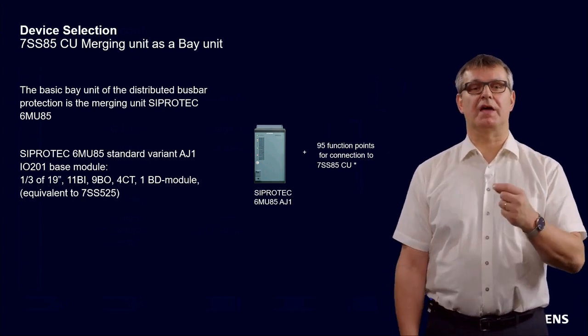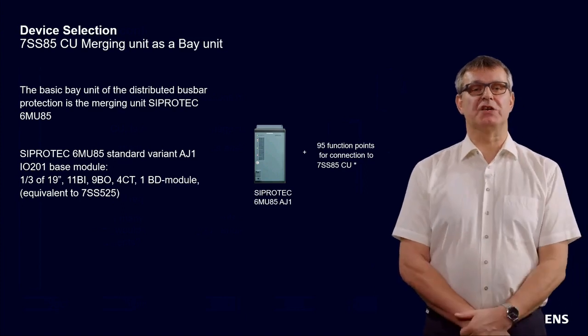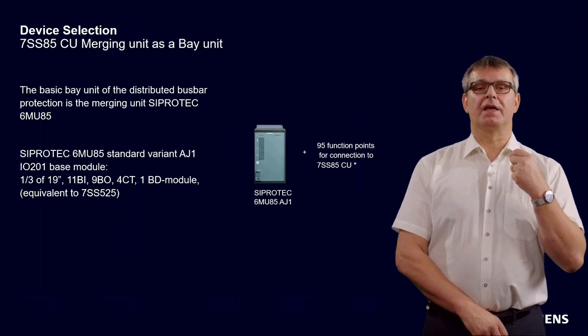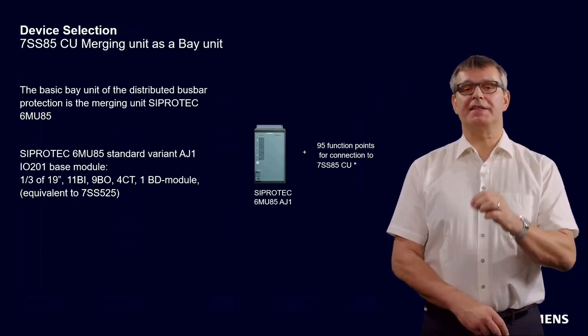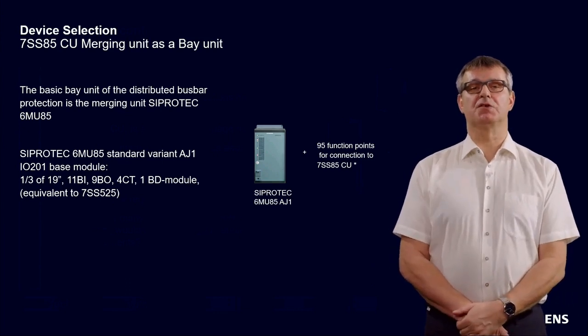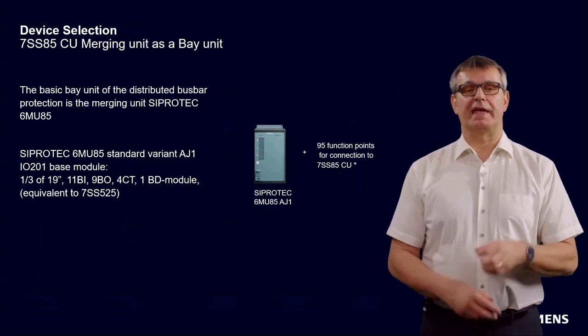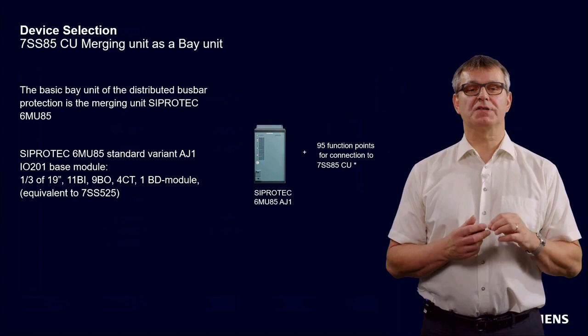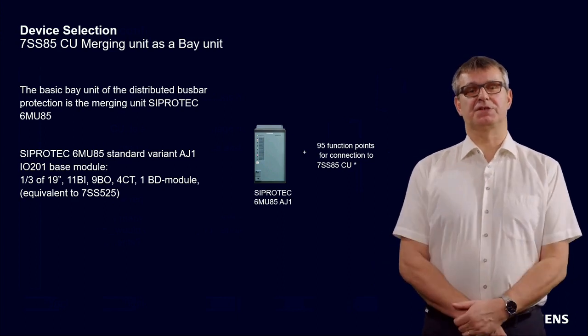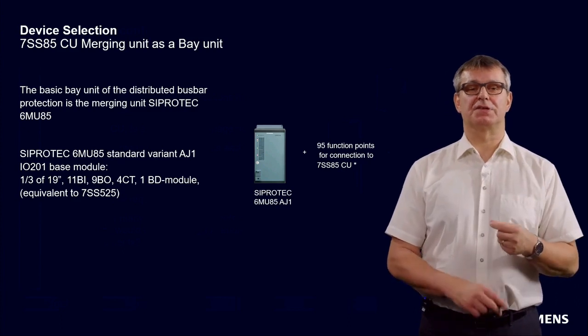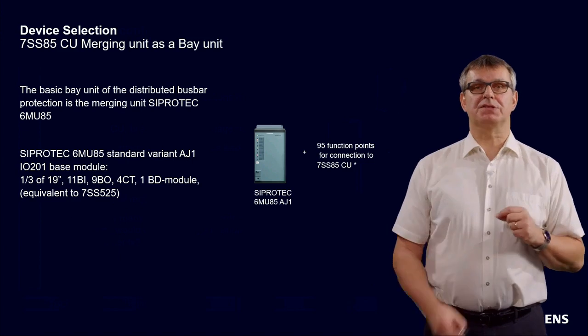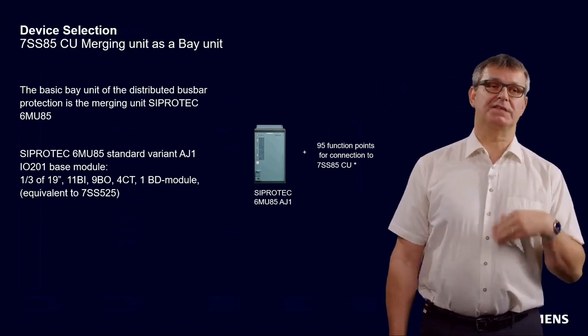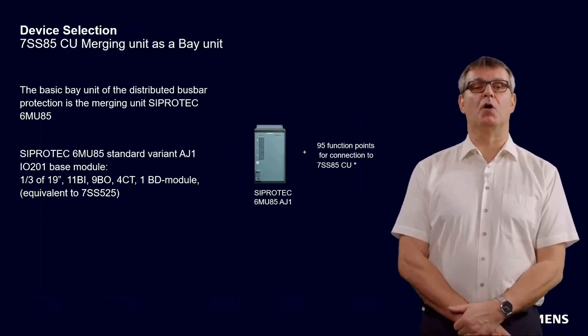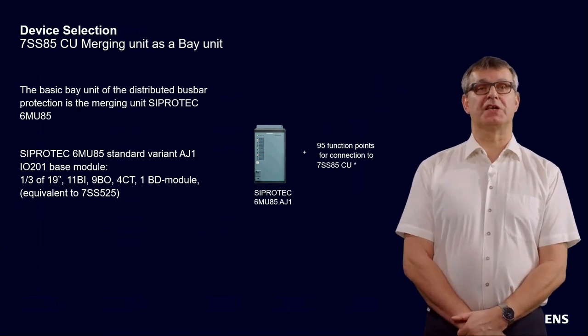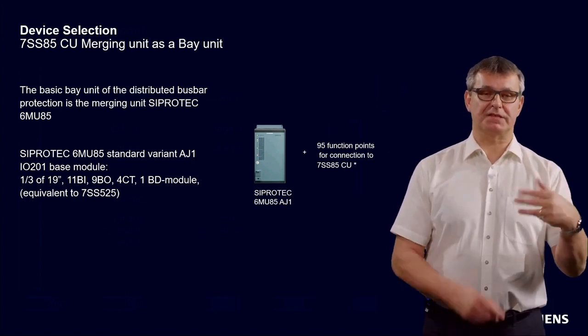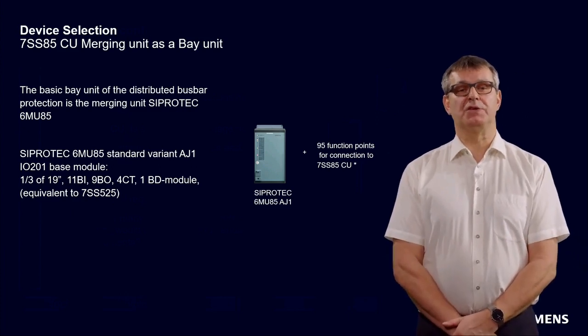You select a 6MU85 in the hardware standard variant AJ1, and then you add 95 additional function points for the connection to the 7SS85 CU. This device configuration is very similar to the small bay unit of the 7SS52, the 7SS525. It offers 11 binary inputs, 9 binary outputs, 4 CTs, meaning 1 current measuring point, and it also brings 1 BD-module, which is mandatory for the communication to the 7SS85 CU. And as already said, that's the same as the small 7SS52 bay unit, the 7SS525.